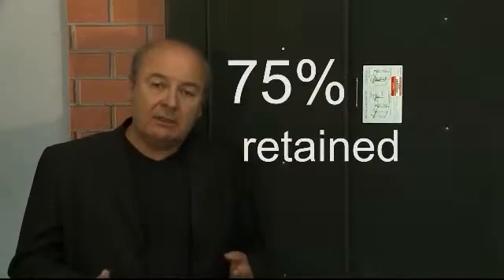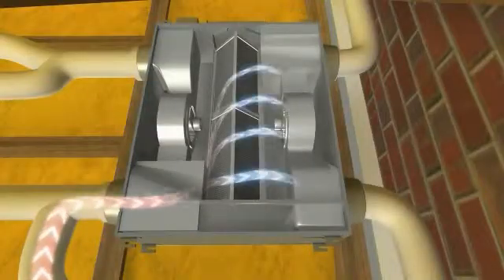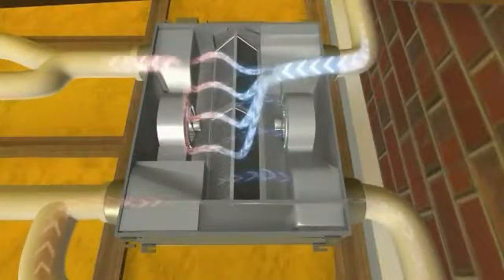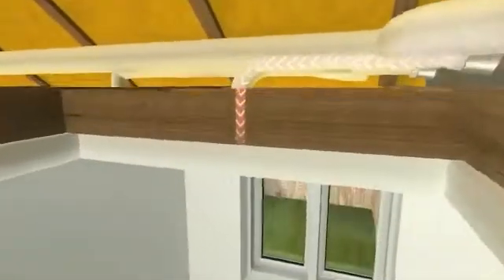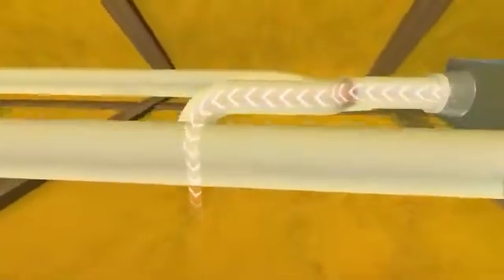That concept is exactly how this core works. This system can trap up to 75% of your domestic heat and push it back into the house. For example, outside air at a winter temperature of 7 degrees is drawn into the unit and mixes with the outgoing air at a comfortable 20 degrees. The Lossnay won't make up the entire difference of 13 degrees, but it will take care of most of it. And when you look at the saving on your fuel bills from that alone, it will give you a warm glow.